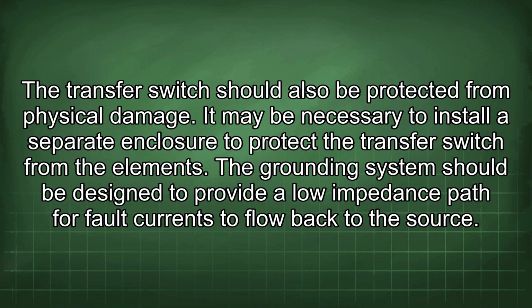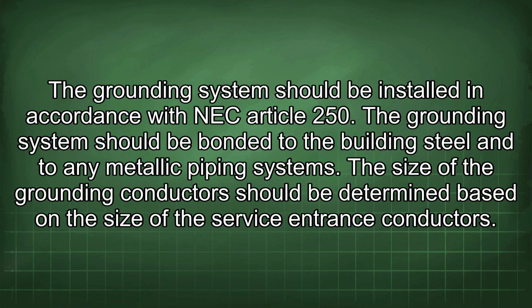The grounding system should be designed to provide a low impedance path for fault currents to flow back to the source. The grounding system should be installed in accordance with NEC Article 250. The grounding system should be bonded to the building steel and to any metallic piping systems. The size of the grounding conductors should be determined based on the size of the service entrance conductors.